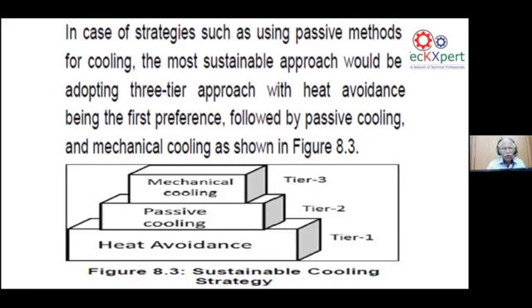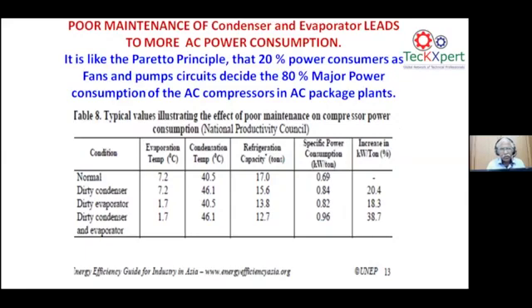It has come down to almost 0.5 to 0.7 kilowatt per ton, instead of 1 to 1.5, thanks to the 3 tiers of cooling strategies employed in all the building establishments. If you see the Pareto Principle, the 20% power consumers, the fans and pumps, are the reason for 80% of the major power consumption of the AC compressors, especially with a dirty condenser or a dirty evaporator.